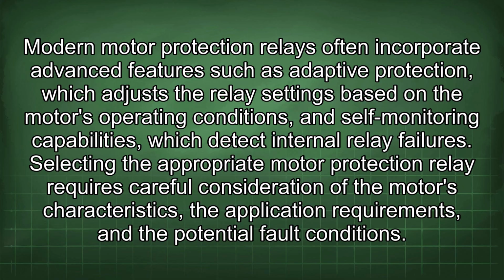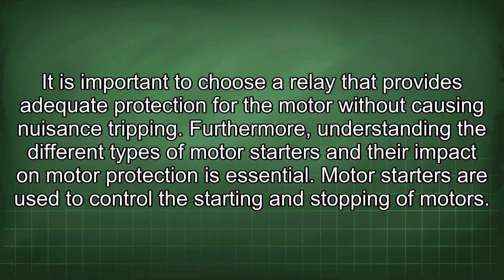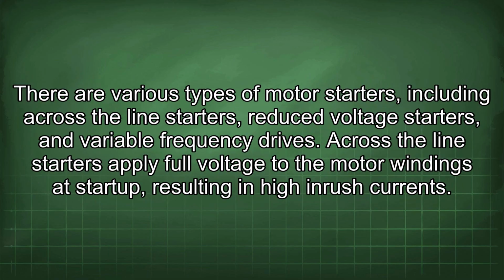Selecting the appropriate motor protection relay requires careful consideration of the motor's characteristics, the application requirements, and the potential fault conditions. It is important to choose a relay that provides adequate protection for the motor without causing nuisance tripping. Furthermore, understanding the different types of motor starters and their impact on motor protection is essential. Motor starters are used to control the starting and stopping of motors. There are various types of motor starters, including across-the-line starters, reduced voltage starters, and variable frequency drives.